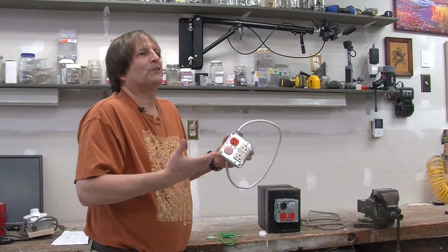And when you're working on that device and it is protected with a GFCI, the innards of that device are still connected to the mains live wire. And by having the chassis not grounded, you can prevent the situation where you happen to be touching the chassis with your hand, grounding yourself particularly well, and then touching something live and getting a good strong zap before the GFCI has time to trigger.